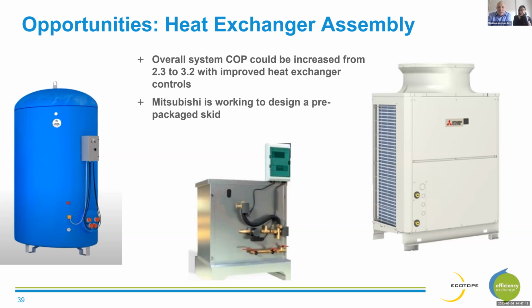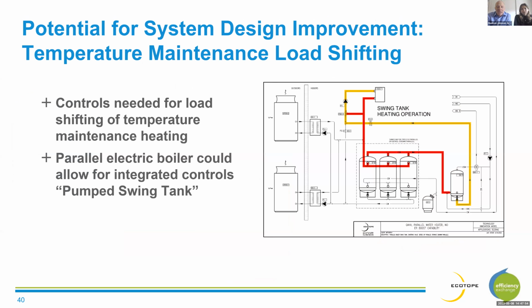The problems that we identified getting cold water on the other side of the heat exchanger into the heat pump have been fed back to Mitsubishi, and they're working on pre-packaging the heat exchanger control and pump assembly into that device that you see in the middle on the slide as a pre-manufactured piece that will help optimize that pumping and temperature management to get COPs above about 3, is what we think we can do with that once Mitsubishi completes their manufacturing of that.